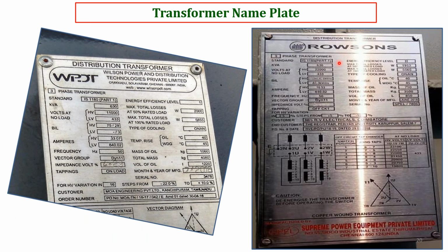Now, this is a nameplate of an IS 1180 energy efficient transformer, where we have 3 levels available: level 1, level 2, level 3. Based on the level, the individual losses will vary, and similarly the pricing of the transformer also varies.